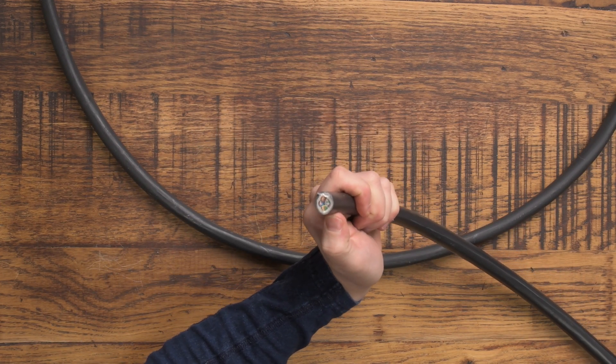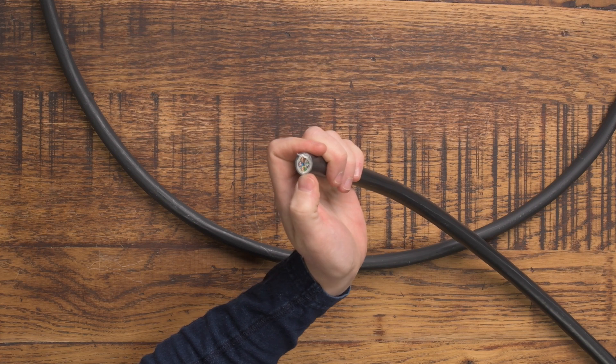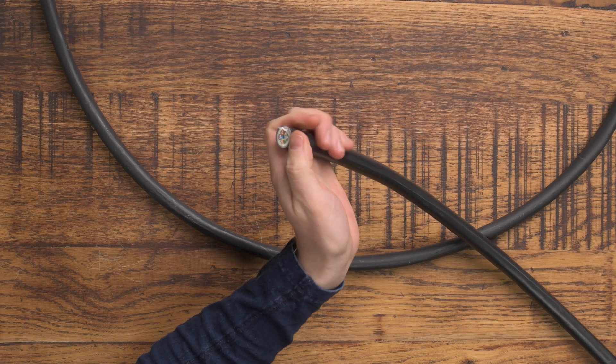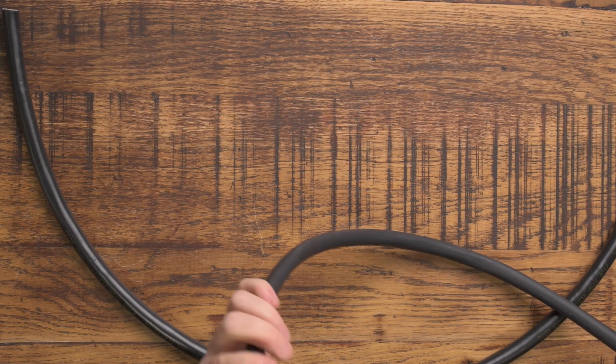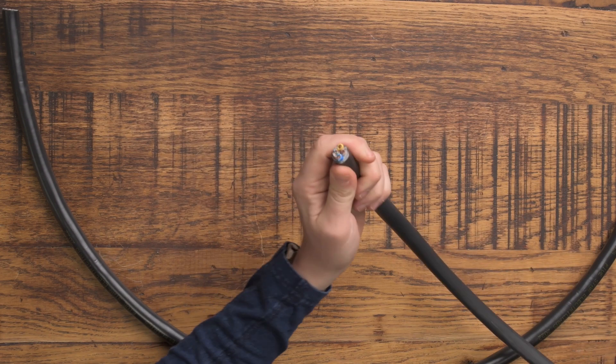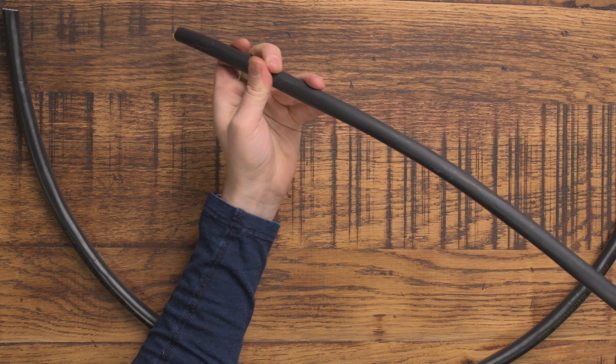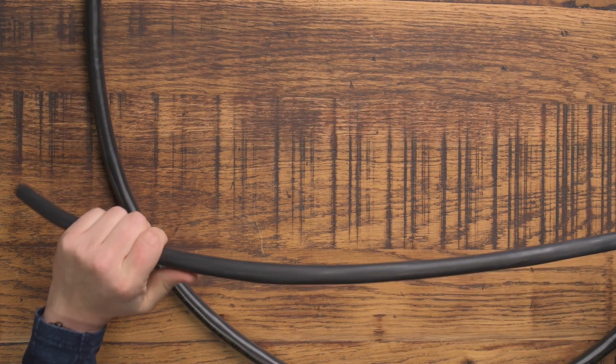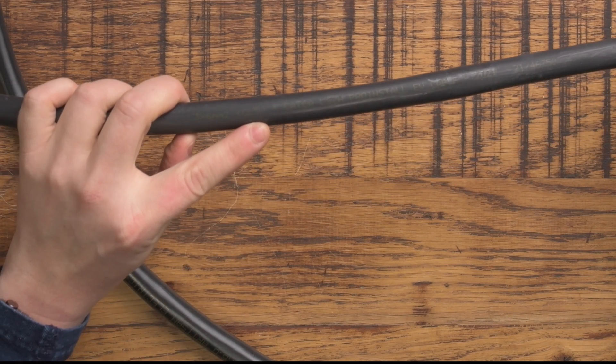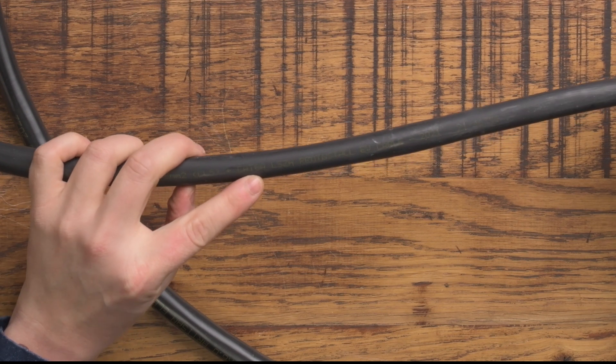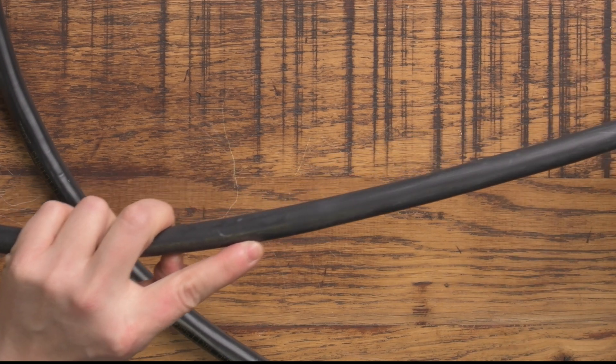So it's a NYYJ or Tuft sheath with three core six millimeter inside and a Cat5 data cable. The other version here is exactly the same, three core six millimeter, but they claim that it's got a Cat6 data cable inside. It says three times six millimeters squared plus Cat6A LSZH Pro install EV cable 2021.